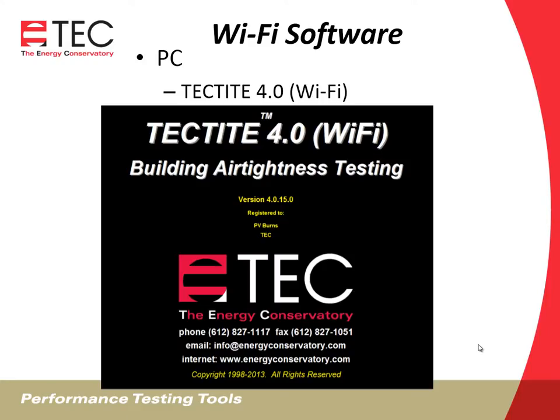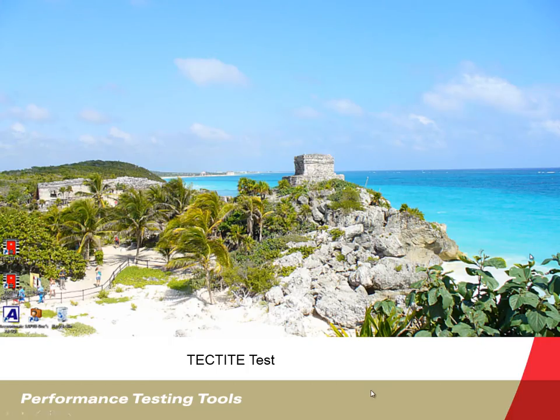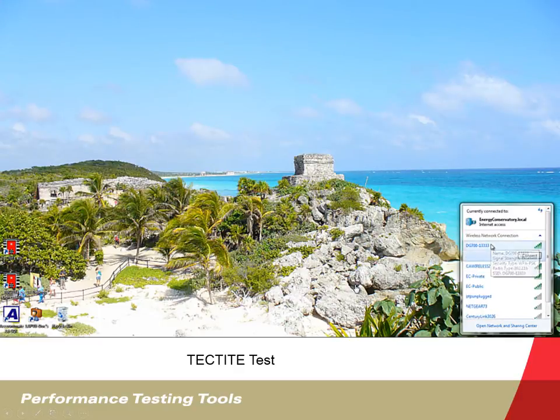The PC software is TECTITE 4.0 Wi-Fi. To connect your PC, on your laptop computer select and connect to the TEC Wi-Fi Link wireless network. The network will be named DG700 followed by the serial number of the DG700. The first time you connect to this network, you'll be asked for a password security key — it's always TEC Wi-Fi 12. Then connect to the DG700 with its serial number and open up the TECTITE software.